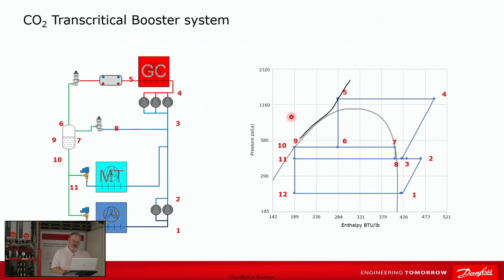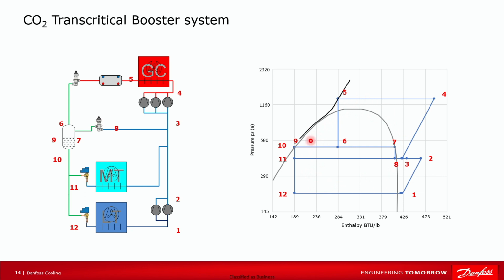So to tie all of those together, here is a diagram on the pH diagram without all the temperature and pressure lines to cause confusion. On the left is a basic system for transcritical booster. We're going to start at point 1 here, and we're going to fill this in on the right. From 1 to 2 is going across the low temp compressors, so we moved up to point 2. Then we desuperheat a little when the discharge gas gets in that lower temperature header. Then we enter the medium temp suction and go across the medium temp compressors. We're now up to gas cooler pressure.